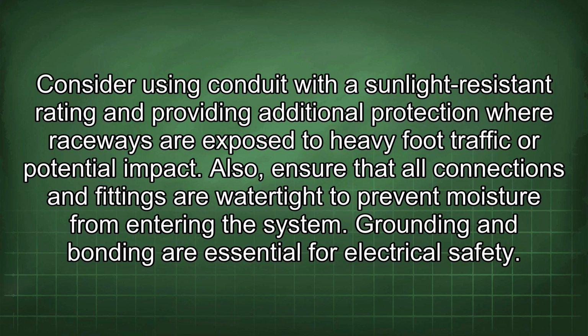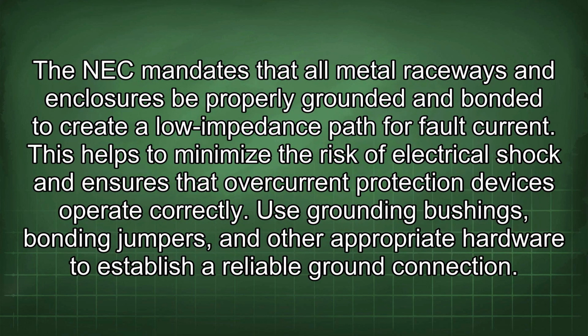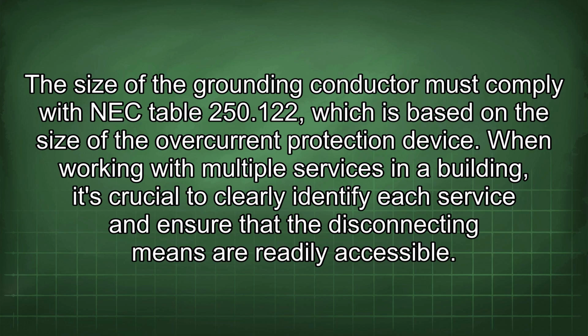Grounding and bonding are essential for electrical safety. The NEC mandates that all metal raceways and enclosures be properly grounded and bonded to create a low impedance path for fault current. This helps to minimize the risk of electrical shock and ensures that overcurrent protection devices operate correctly. Use grounding bushings, bonding jumpers, and other appropriate hardware to establish a reliable ground connection. The size of the grounding conductor must comply with NEC Table 250.122, which is based on the size of the overcurrent protection device.